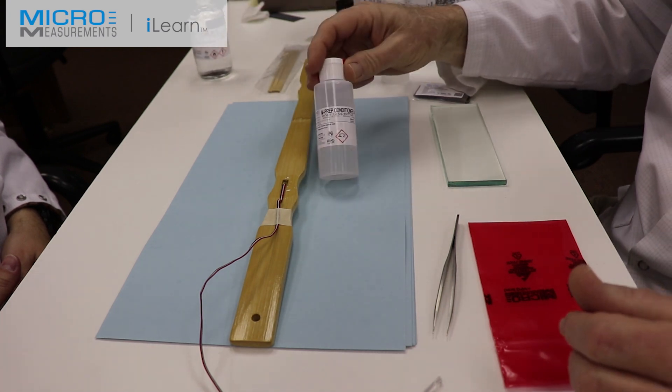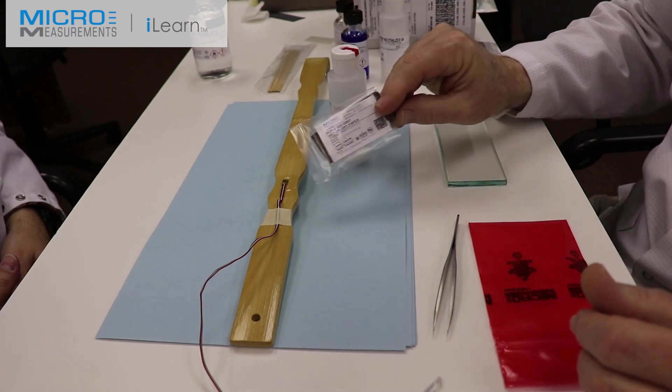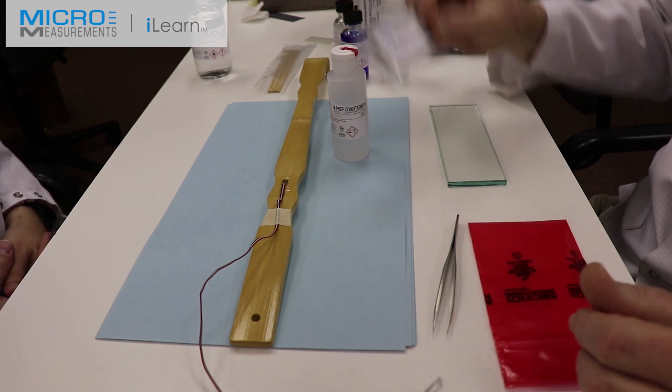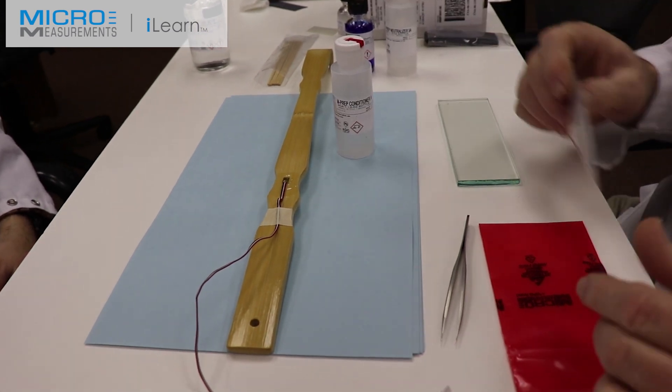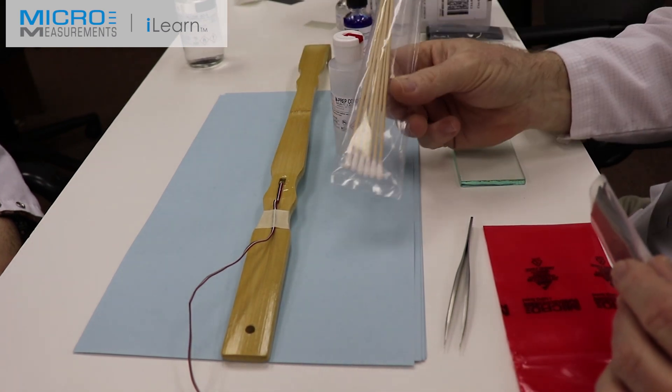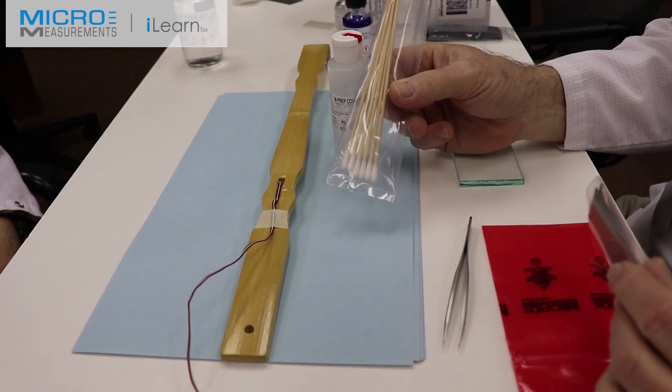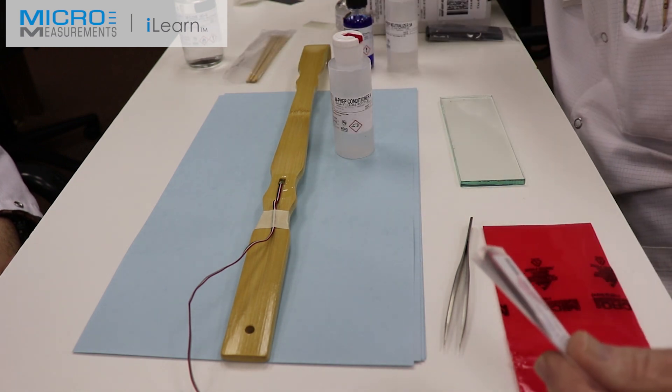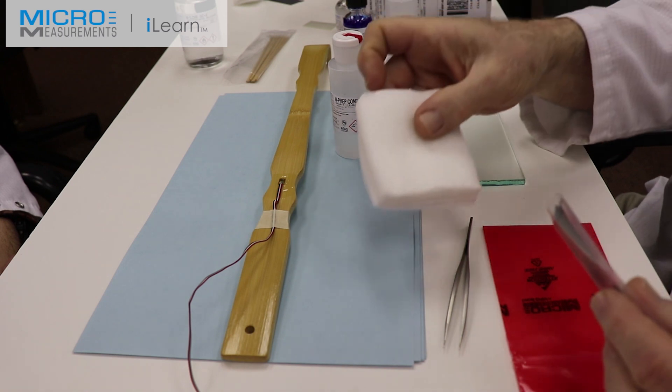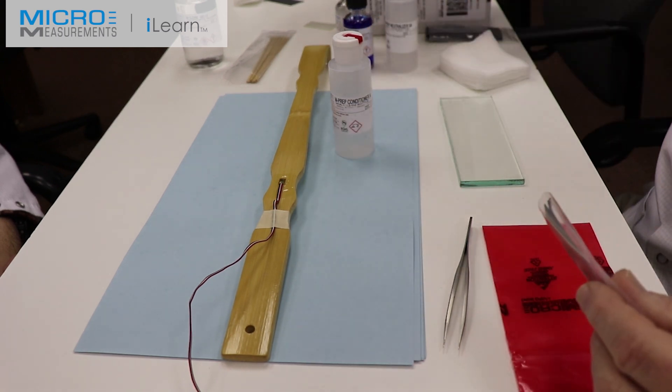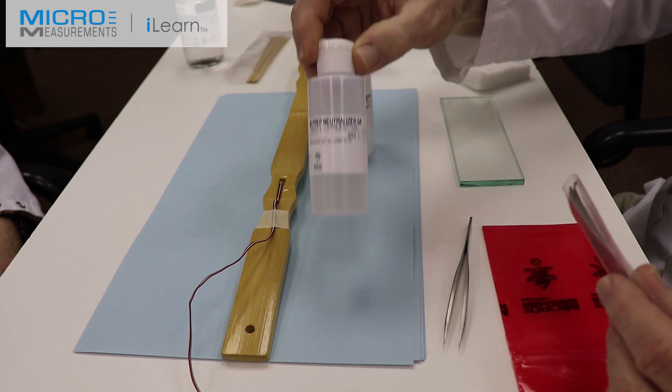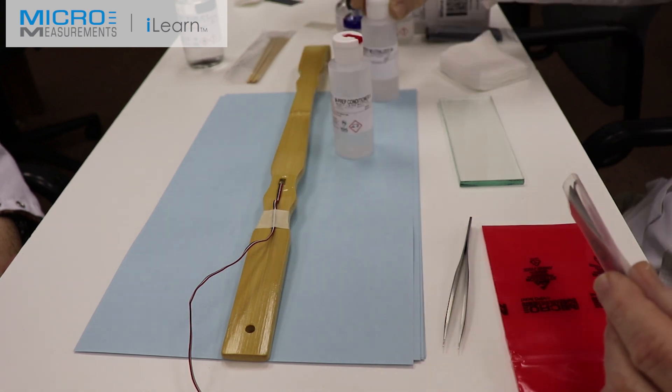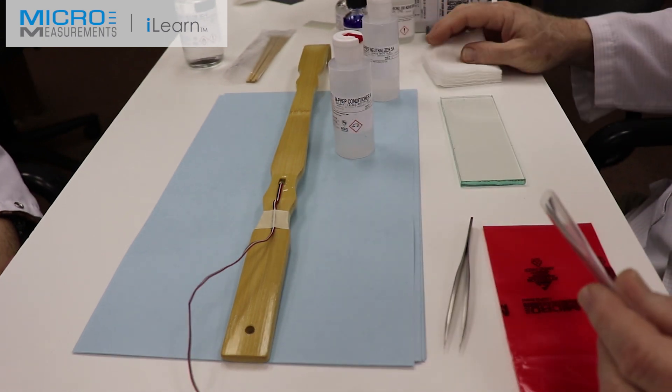We used the Conditioner A and the SCP-2, the silicon carbide abrasive paper. We used it to dry-abrade, then wet-abraded with Conditioner A, and then scrubbed using the cotton tip applicators, CSP-1. We scrubbed with Conditioner A and wiped it dry with gauze sponges, the GSP-1. Then we scrubbed with Neutralizer-5A to get the surface proper pH for bonding, and used gauze sponges to dry the surface.